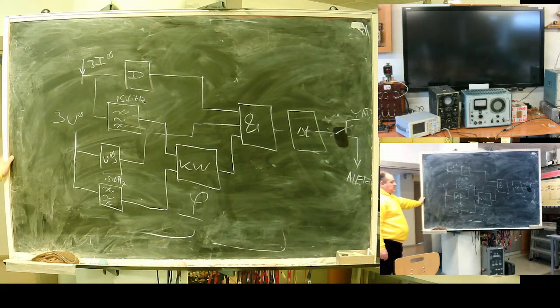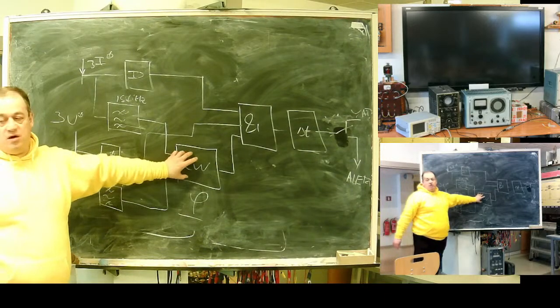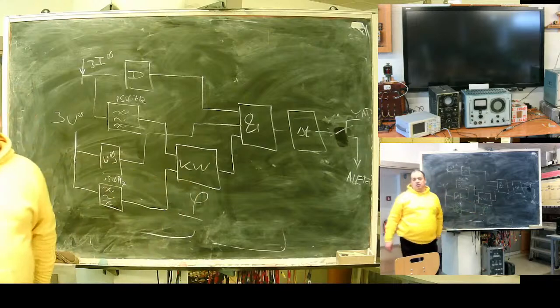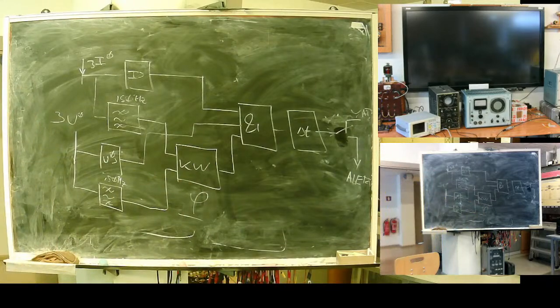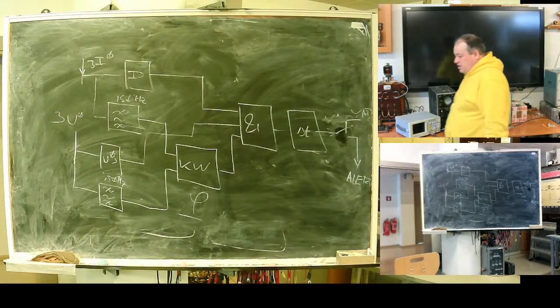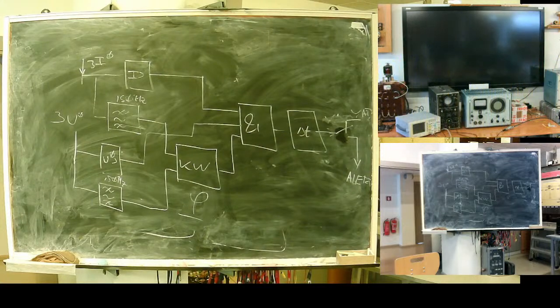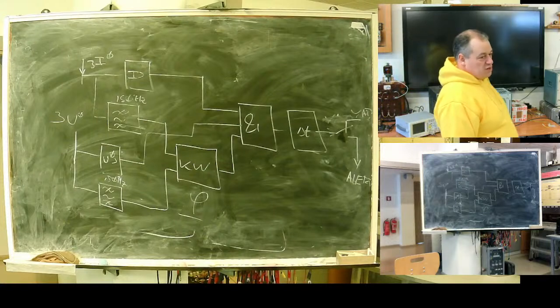Here is the schematic for such a relay. So, the angle function here sits on the third harmonic. But there should be a sufficient level of third harmonic. It works very well in metal factories or where there is large industrial penetration, and not always in rural areas.